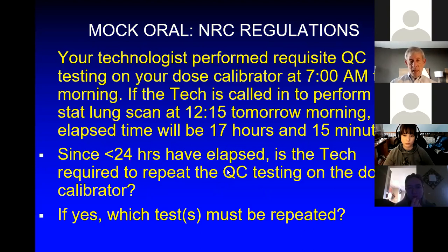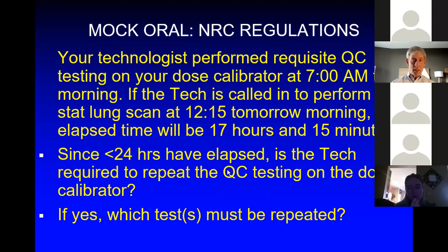Okay. Let's say you came in this morning, 7 a.m., and checked your dose calibrator. It's working fine. Now, if you are called in at 12:15 tomorrow morning, that's a little over 17 hours, you're going to do, let's say, a stat lung scan. It's already the next day. What is the requirement for repeating the dose calibrator test?